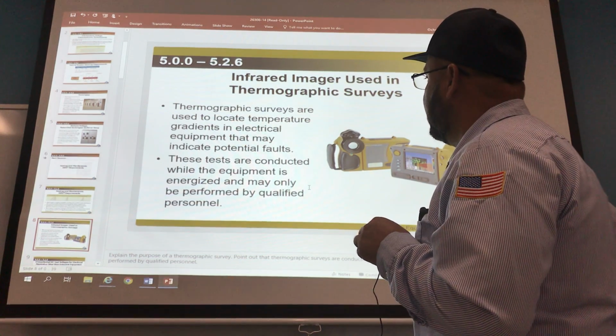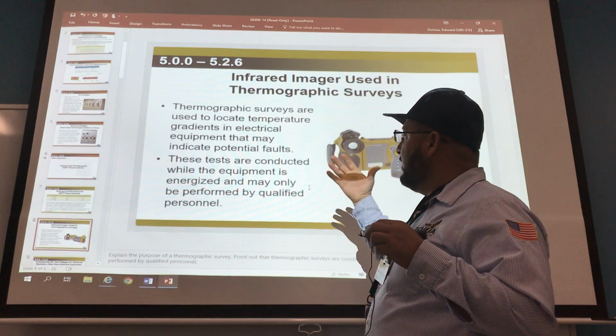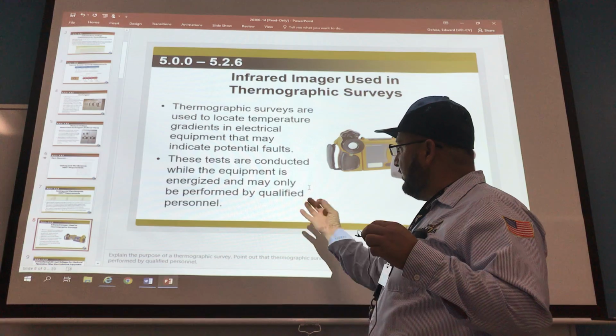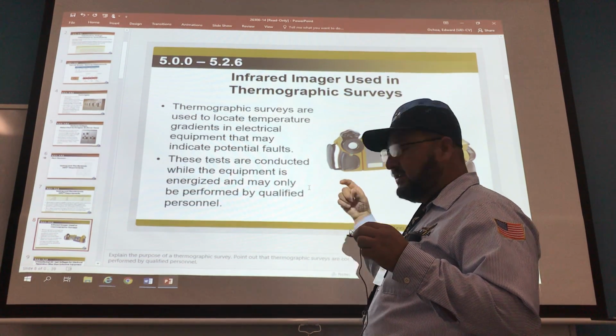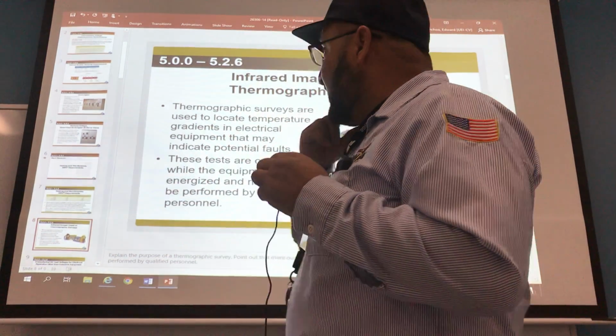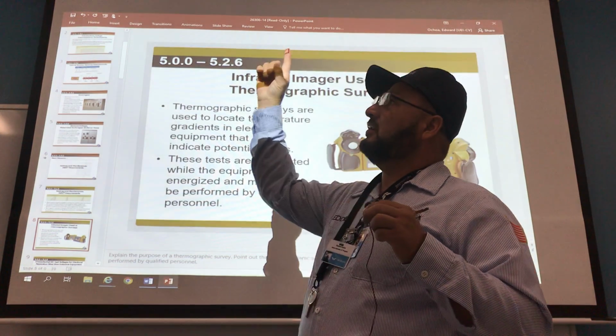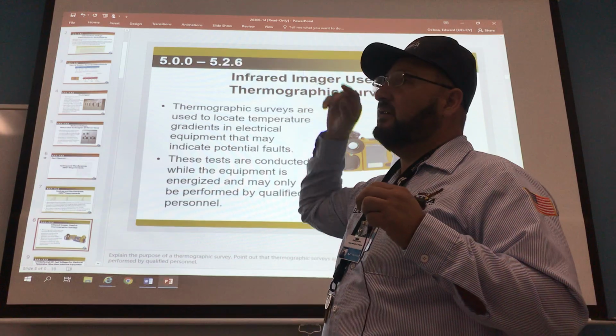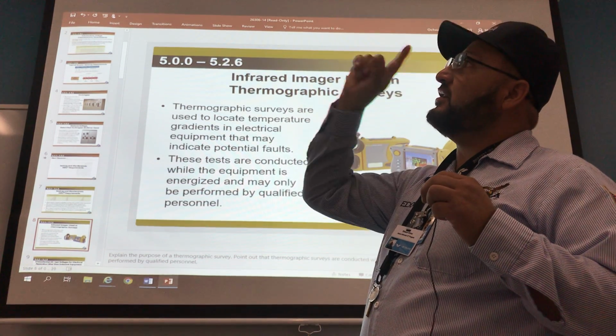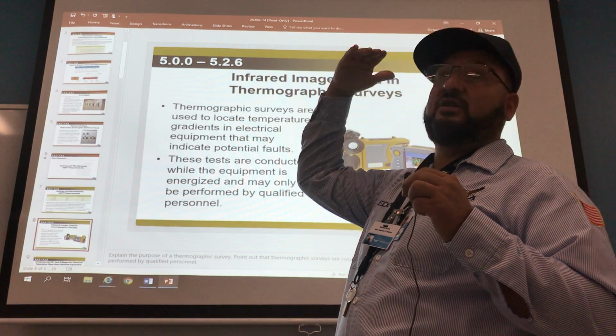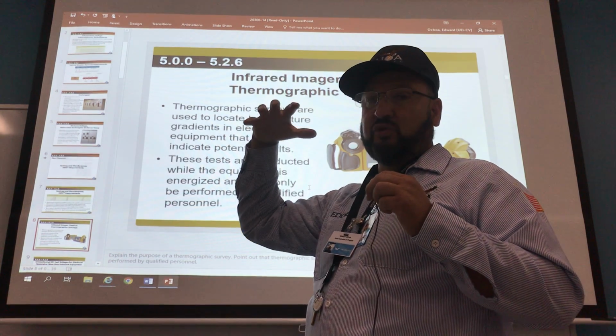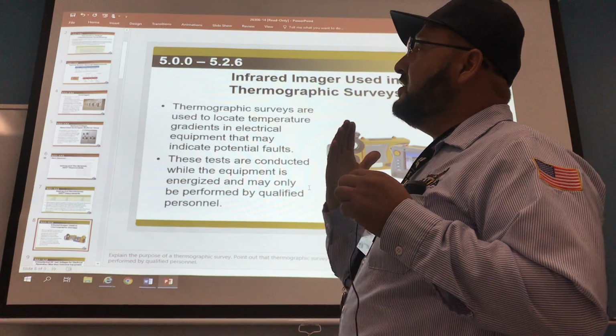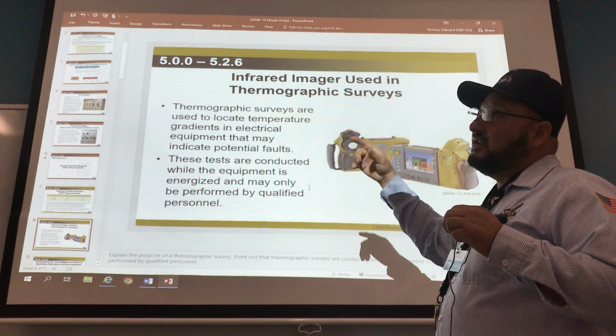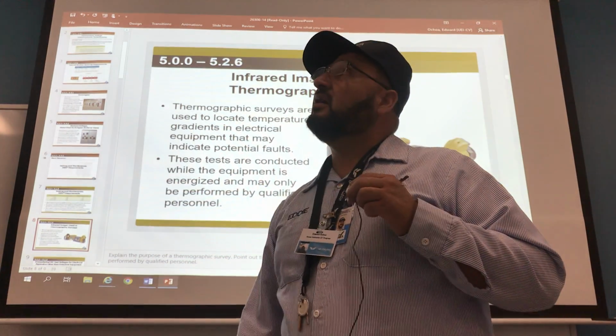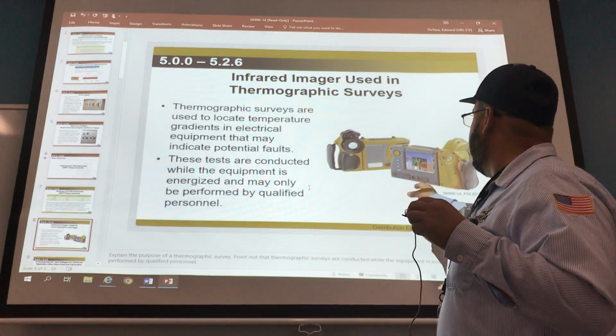The one I have, I paid $600 for, and it identifies hot points at each connector. If you have power coming in, it'll show at each lug the heat around it, and it gives a temperature reading too, so you have an idea of what's going on. This is also great for infrared imaging of radiant heating in the ceiling. You put it up to the ceiling and you can actually see the lines where the radiant heat is coming from, even though you can't physically see or really feel it since it's not that strong. It's a comfortable heat, but you can't see what's wrong with it normally. With this tool, you can actually see the heat lines. I have some pictures to show you. This is a very valuable piece of equipment to help with troubleshooting.